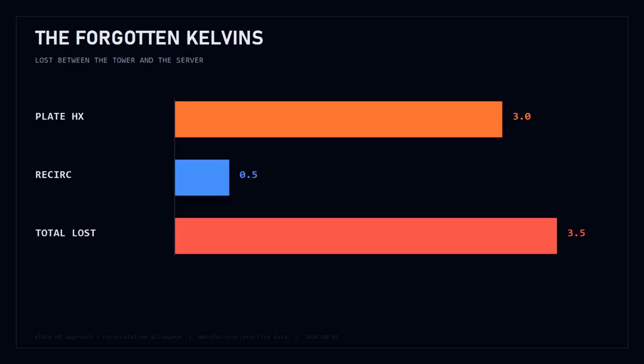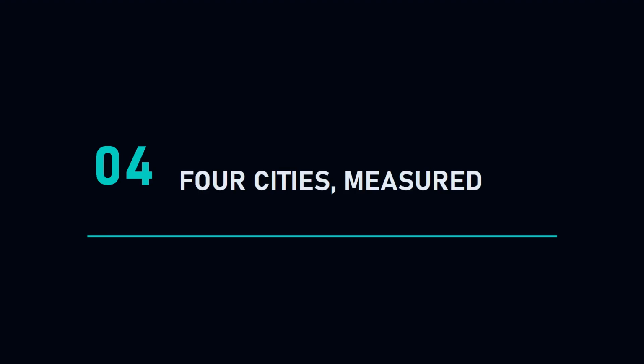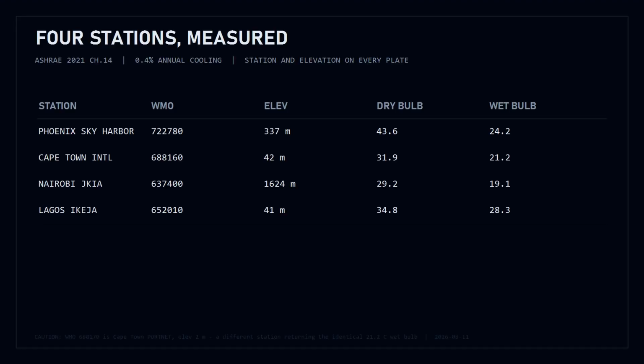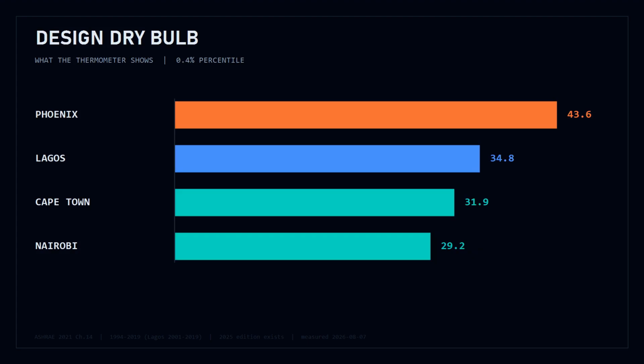And here is the piece almost every explanation drops. Between the tower and the room, there is usually a plate heat exchanger with an approach of its own, around 3 Kelvin. Add a recirculation allowance, roughly half a Kelvin more, 3.5 Kelvin, gone before the water reaches a single server. That does not sound like much. Watch what it does. 4 cities: Phoenix, Cape Town, Nairobi, Lagos. Design conditions, ASHRAE 2021. The 0.4% percentile, the condition exceeded about 35 hours in an average year. Dry bulb first. Phoenix 43.6, Lagos 34.8. Phoenix is 8.8 degrees hotter.